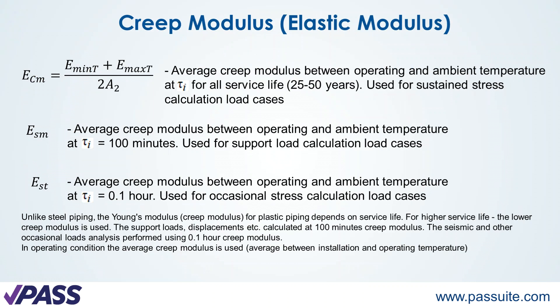We have three types of creep moduli. The first creep modulus is used for sustained stress calculation and is calculated for the full service life — for example, 25 or 50 years as you wish. You can set this parameter in the project settings in START-PROF. This creep modulus is calculated as the average value between operation and cold temperature. The second creep modulus is calculated for 100 minutes and is used for support load calculation.